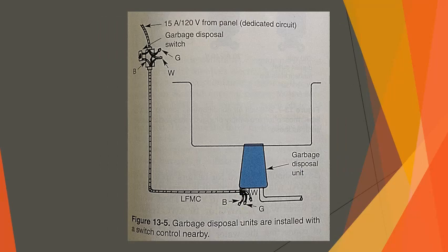Garbage disposal unit. Garbage disposal units, such as the one pictured in 13-5, may be controlled directly from the panel circuit breaker, from a plug and cord connection, or most often with an on and off switch. They are rated at approximately 5 to 10 amps and 120 volts. Since garbage disposals must have overcurrent protection not exceeding 125% of their motor's full load current rating, a 15 or 20 amp breaker is usually sufficient.